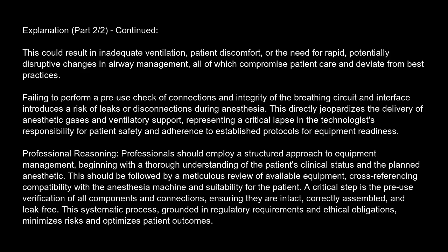Failing to perform a pre-use check of connections and integrity of the breathing circuit and interface introduces a risk of leaks or disconnections during anesthesia. This directly jeopardizes the delivery of anesthetic gases and ventilatory support, representing a critical lapse in the technologist's responsibility for patient safety and adherence to established protocols for equipment readiness.